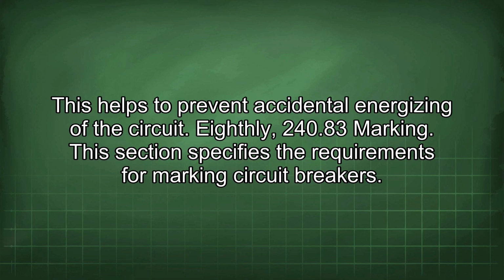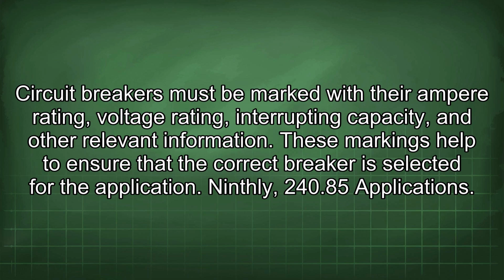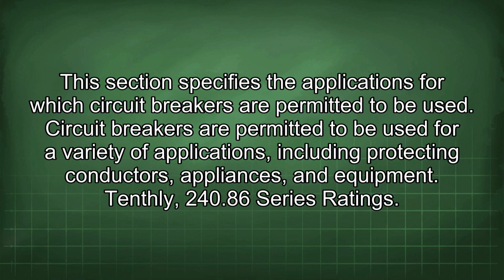Eighthly, 240.83 Marking. This section specifies the requirements for marking circuit breakers. Circuit breakers must be marked with their ampere rating, voltage rating, interrupting capacity, and other relevant information. These markings help to ensure that the correct breaker is selected for the application. Ninthly, 240.85 Applications. This section specifies the applications for which circuit breakers are permitted to be used. Circuit breakers are permitted to be used for a variety of applications, including protecting conductors, appliances, and equipment.